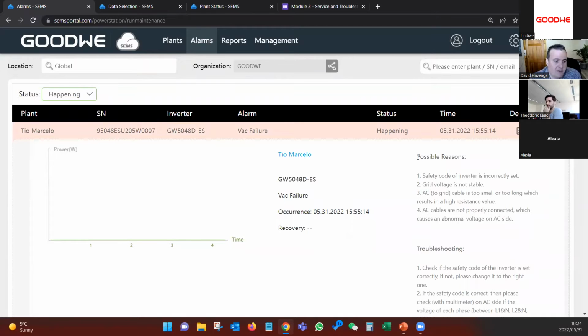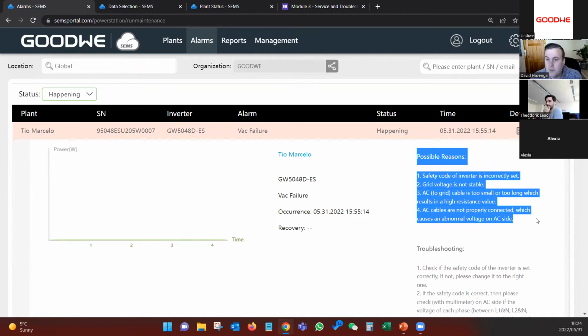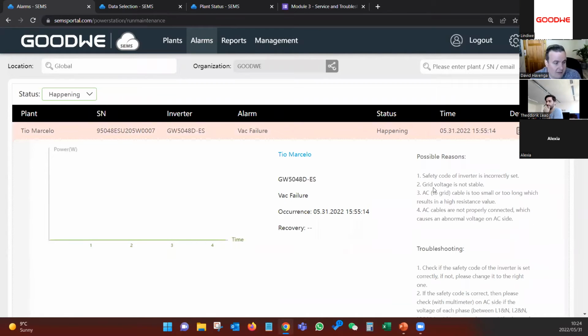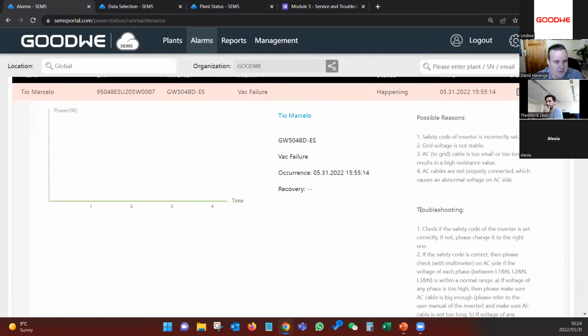So in here, we also do have a bit of a FAQ and possible things that could be resulting in exactly what's happening on the device. As you'll see, the majority here is the VAC failure. That's most of the time, that's why we have hybrids in many countries, to have power when the grid fails. But you'll see there's possible reasons why it happened and troubleshooting.